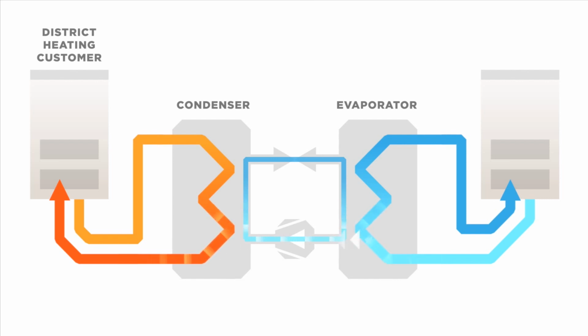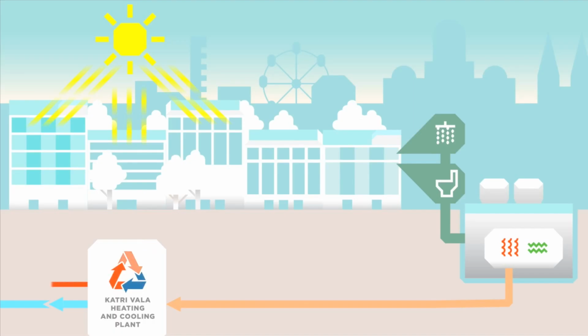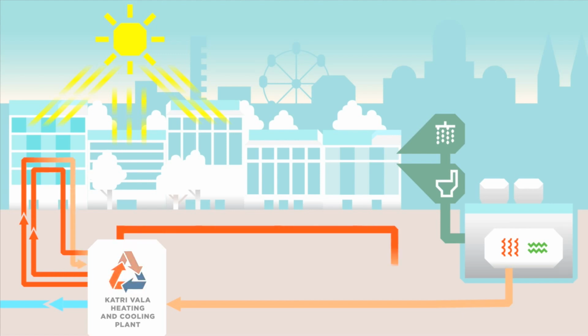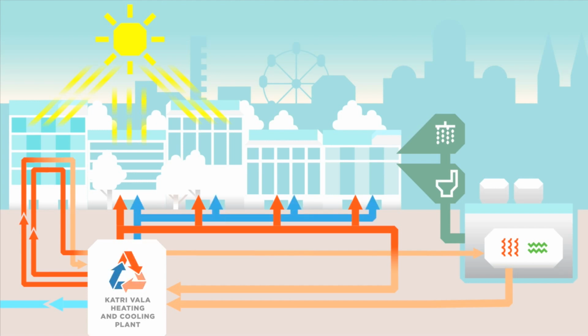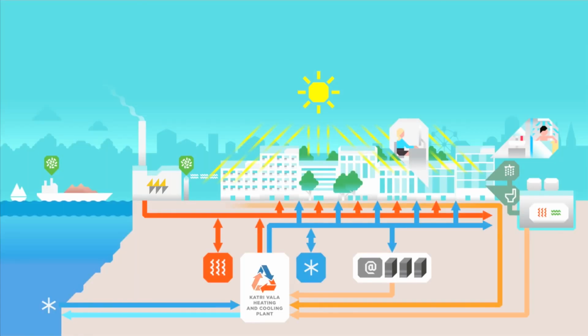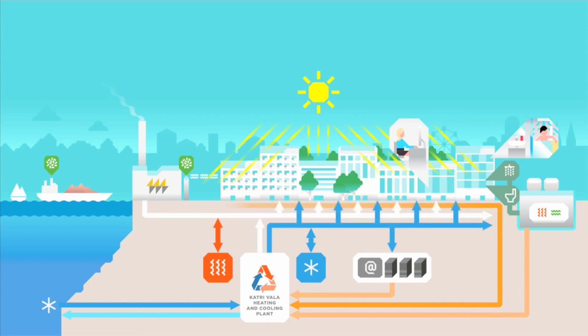In the evaporator, it cools down the return water from the district cooling to about 4 degrees to be used as supply water in district cooling. The compressor raises the pressure of the steam, which then moves back to the condenser, continuing the same circulating process. In cold seasons, the plant produces district heat for the heating of homes and hot tap water using heat pumps and the waste heat of sewage water. District cooling is produced from cool seawater and with heat pumps. In warmer seasons, the Katrivala heating and cooling plant produces mainly district cooling and also some district heat for the supply of hot tap water.